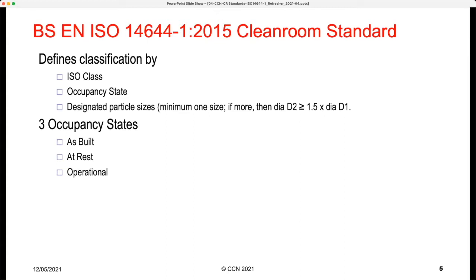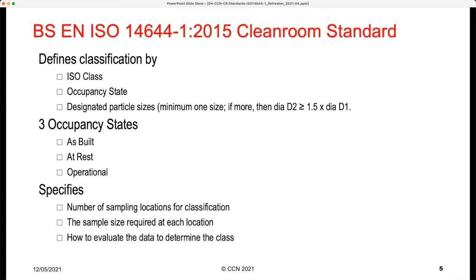It is up to you to choose one or more occupancy states depending on what you wish to achieve — it may be that a regulation or customer requires an as-built test, at rest, operational, or a combination. You must always define the occupancy state. The standard also specifies the minimum number of sampling locations, the air sample size required at each location, and how to evaluate the data.